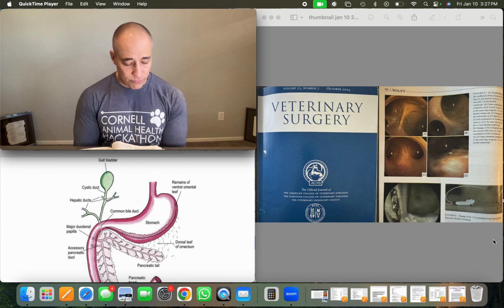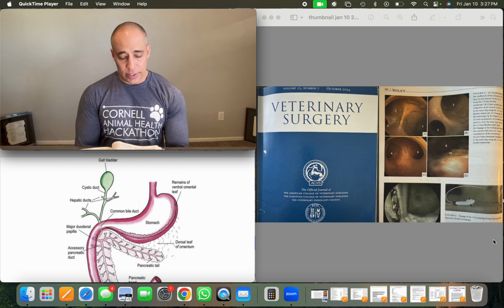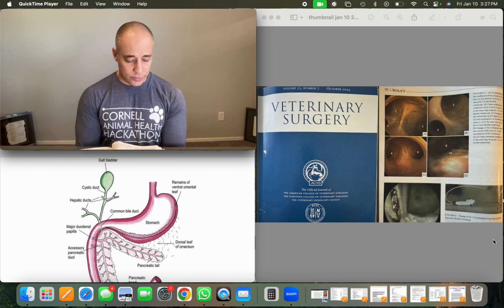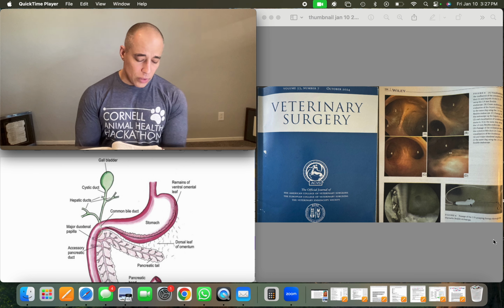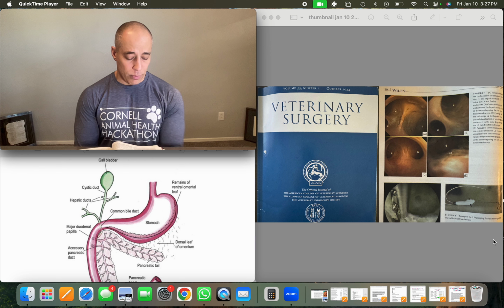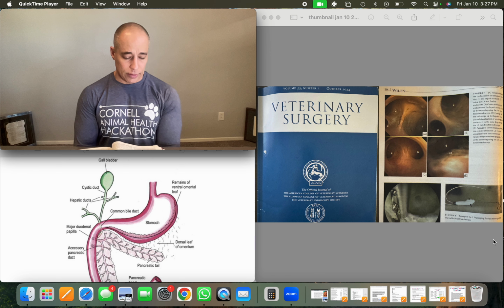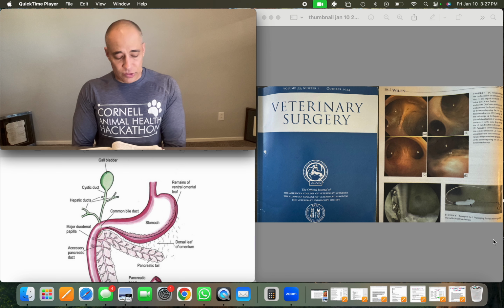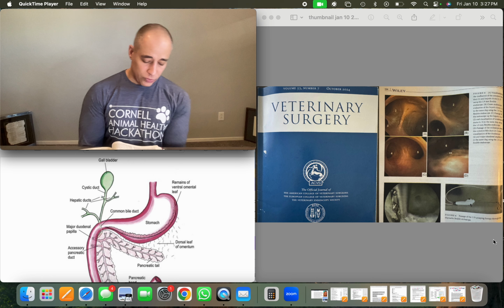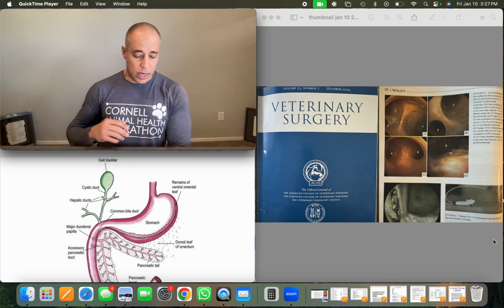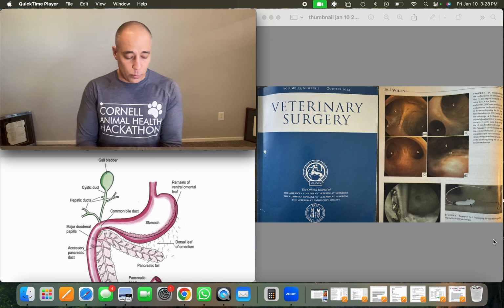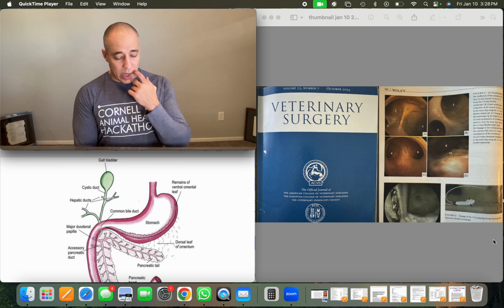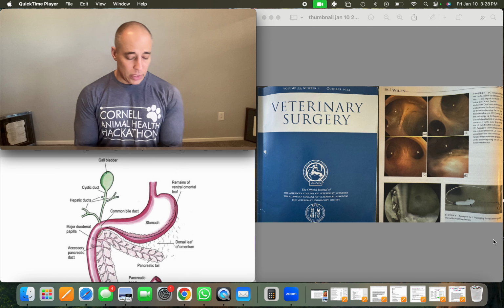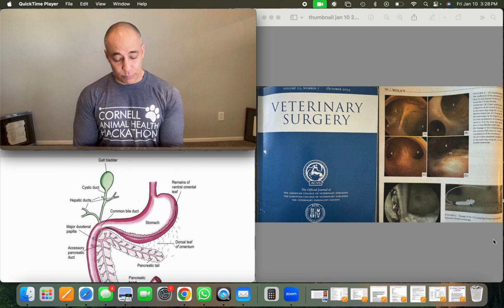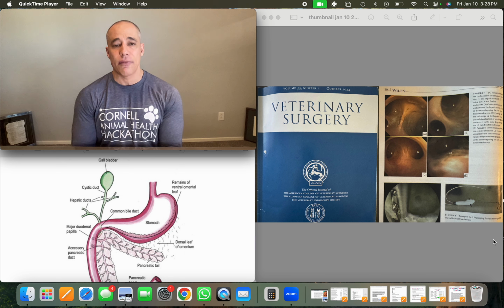Patency assessment can be performed through cholangiography, cholangioscopy, and choledocoscopy. Purpose-made choledocoscopes require significant upfront expense of $50,000, and there's a concern for patient-to-patient infections. Disposable scopes cost about $2,300 for 4 disposable endoscopes. Disposable scopes require less ancillary equipment, as a light source is already embedded in the scope, and a single unit is required for processing and display, about a $5,500 expense.